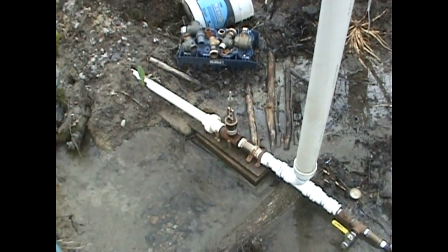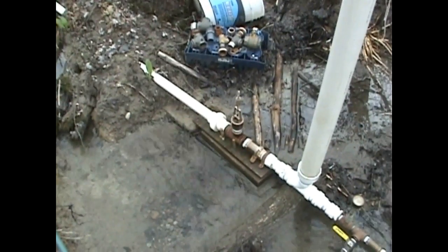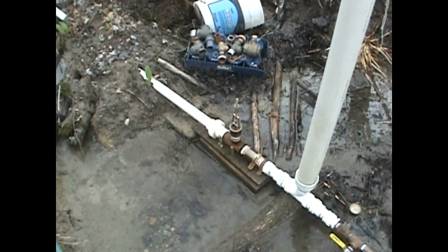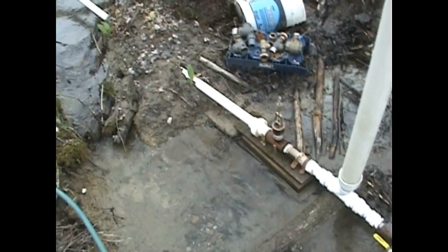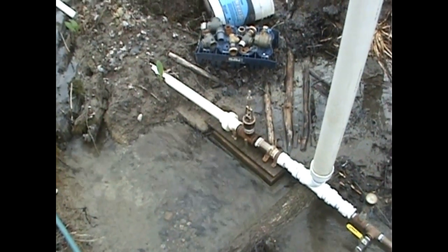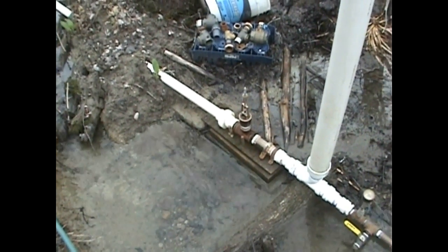And this is an excellent opportunity because I just had a question in the comment section from Dead Dad's Racing Lara, I think is the YouTube handle. He was having trouble with his pump shutting off. It runs for a couple hours and then shuts off. And I said it could be one of two things. It could be air getting into your main delivery pipe or supply pipe, or it could be a leak in the pressure chamber. I suspect in his case it probably is a leak in the pressure chamber.